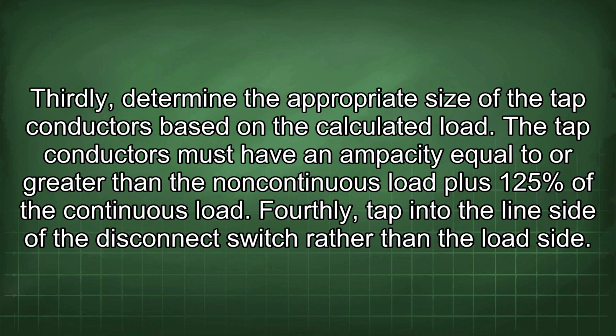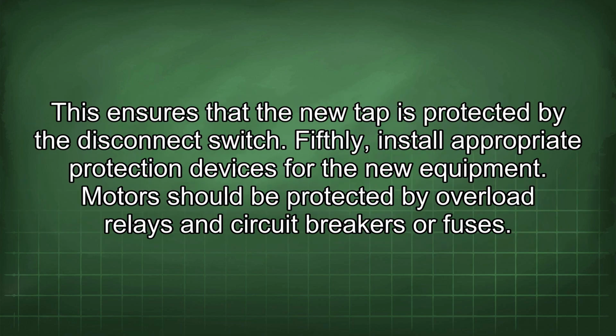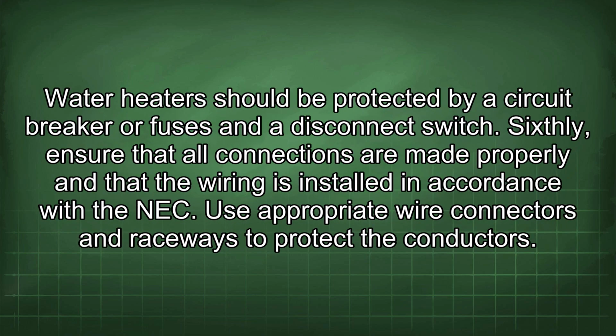The tap conductors must have an ampacity equal to or greater than the non-continuous load plus 125% of the continuous load. Fourthly, tap into the line side of the disconnect switch rather than the load side. This ensures that the new tap is protected by the disconnect switch. Fifthly, install appropriate protection devices for the new equipment. Motors should be protected by overload relays and circuit breakers or fuses. Water heaters should be protected by a circuit breaker or fuses and a disconnect switch.